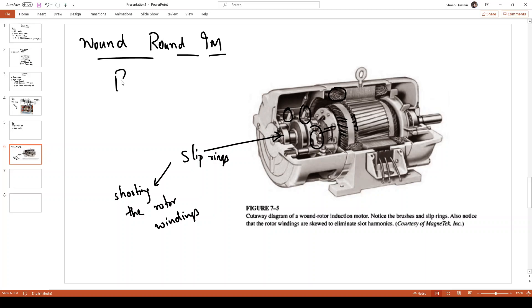In the wound rotor induction motor, the rotor is similar to the stator — it has slots and teeth and carries windings. In a three-phase induction motor the rotor carries three-phase windings similar to the stator. These three-phase windings can be connected in star or delta; they are mostly preferably connected in star. By means of the slip ring and brush arrangement, the windings do not get twisted as the rotor rotates, and we can carry the current forward. The slip rings also allow us to short the rotor windings.